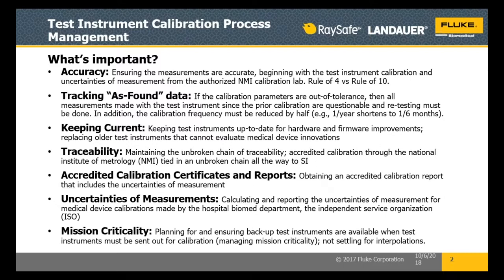A lot of what manufacturers needed to do was in software, so improvements happened quickly without much hardware change. In addition to that, there's the problem with defibrillators — specifically AEDs. In the last five years, we've still had 60,000 incidents of AED failure just when you need it most. That's because by and large we're not testing them enough. More and more of us are, and we're trying to spread the word about what you ought to look at when you're doing it.